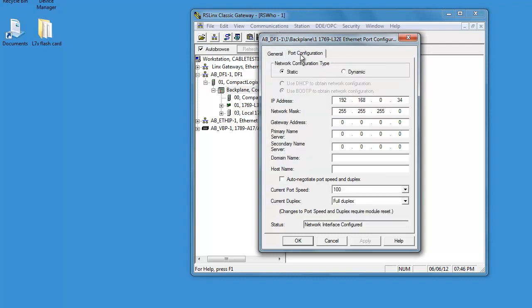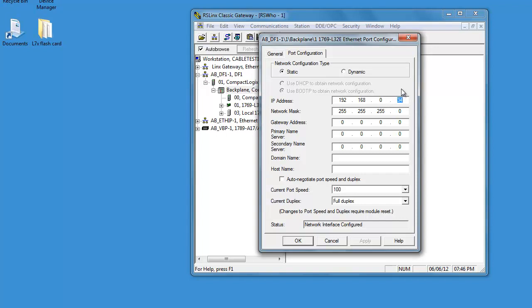So we're going to change the port configuration. Set it up to static 192.168.0.34. Check with your IT department to verify that this is a good number or ping this number to make sure it's not being used on another device on your network or else you'll crash your network if you have two nodes on the same.